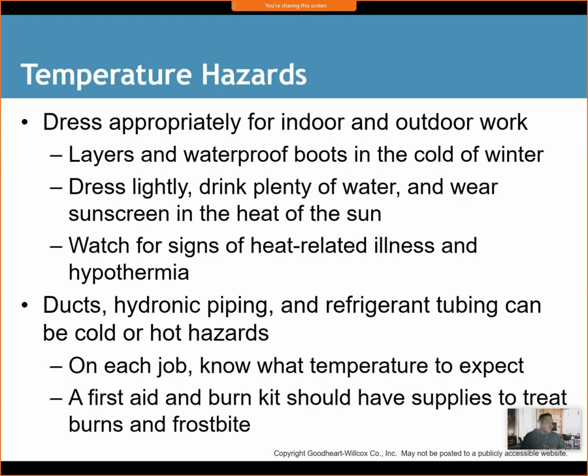Ducts, hydronic piping, and refrigerant tubing can be cold or hot hazards. On a typical refrigeration system, AC-wise, if we're talking about R22, our pressures are going to be anywhere from 60, 70, 80 PSI on the low side, all the way up to 200, 250 on the high side. If we start talking about R410A, the newer type of refrigerant, our pressures start reaching 400 PSI.